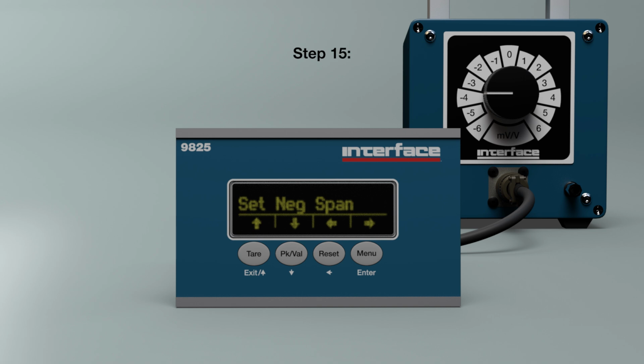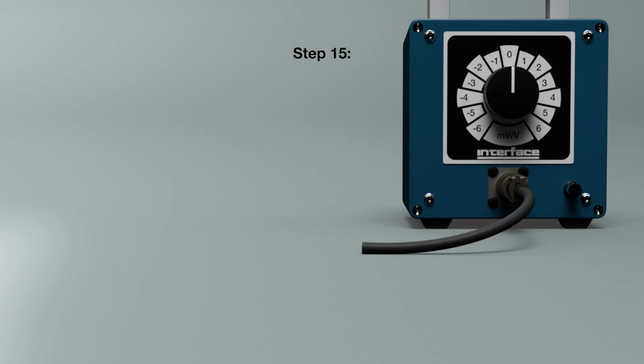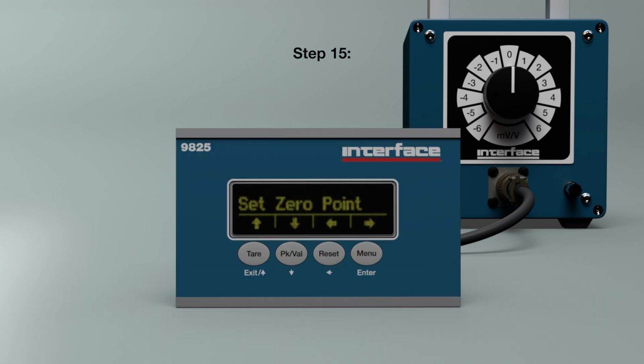Step 15. Press the menu key to scroll right to the next menu item called Set 0 Point. For this example, we will be using a load simulator to set the 0 point value. Make sure that the load simulator is set to 0 millivolt per volt, then press the peak and valley key to capture the 0 point value. A dashed line will migrate across the display as the 9825 records the input. Once the 0 point value has been recorded, the Set 0 Point menu item will be displayed again.